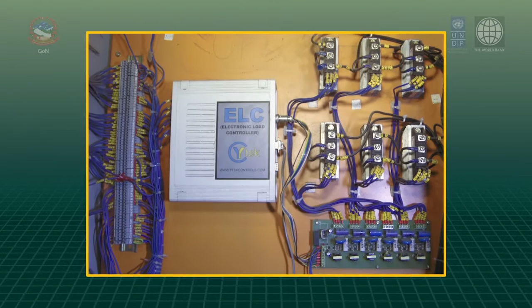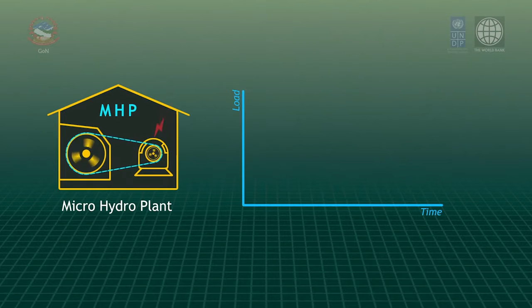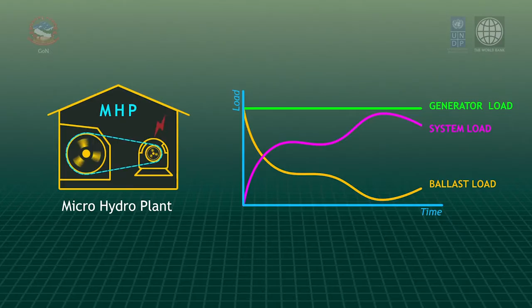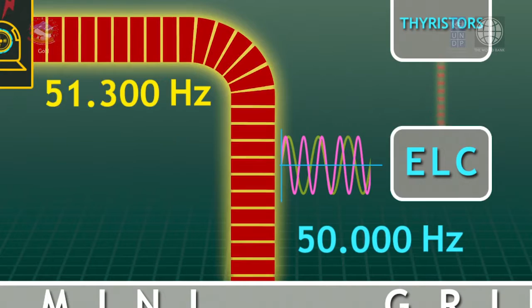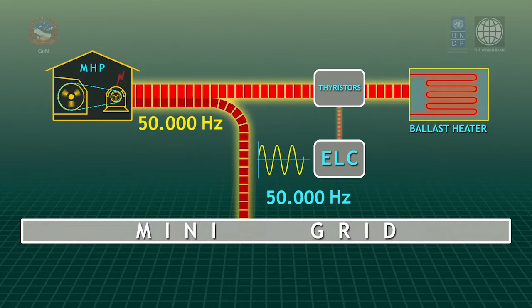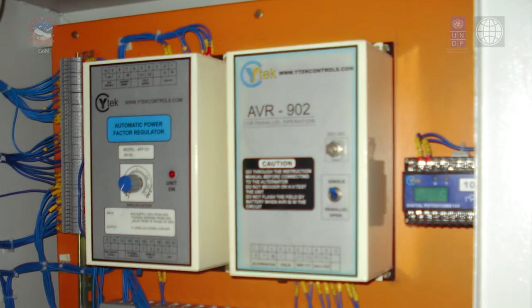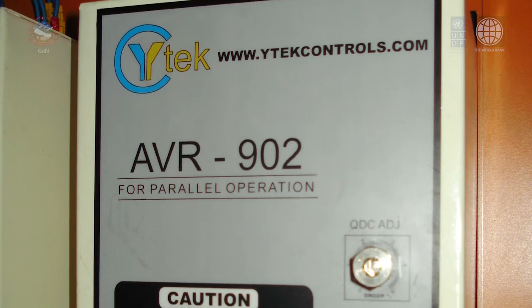Electronic load controller is incorporated in the control panel to govern the frequency of the generator. Electronic load controller maintains constant load to the generator despite the variation of the load in the system. In synchronized mode, electronic load controller tracks the mini-grid frequency and controls the ballast load to maintain the synchronism between mini-grid and the generator. On the other hand, voltage of the generator is maintained by the automatic voltage regulator that controls the excitation of the generator to match the system voltage.